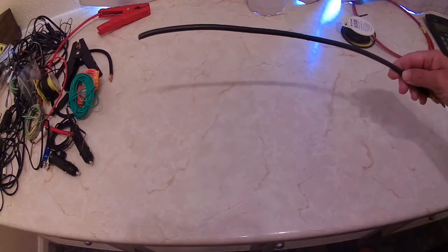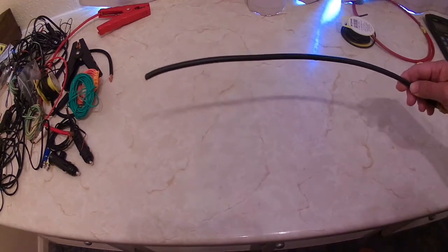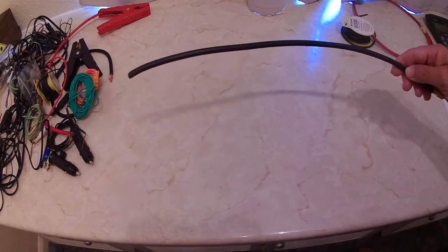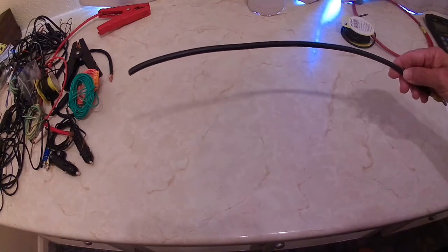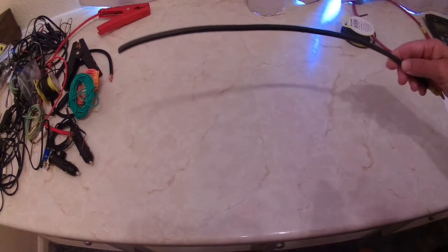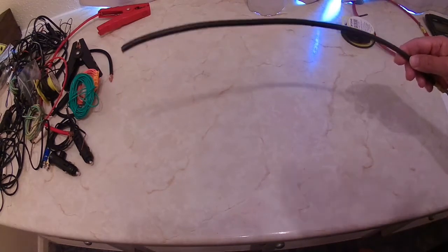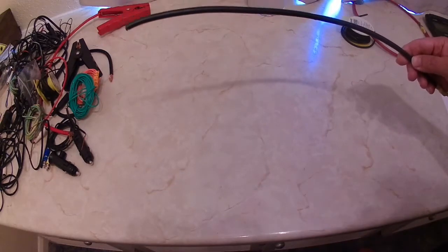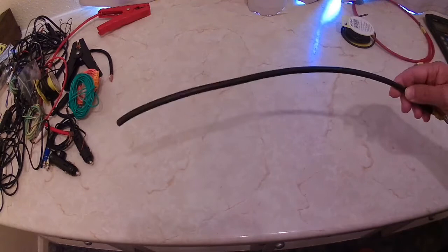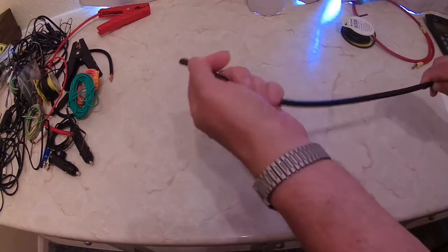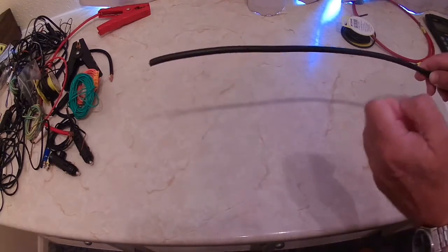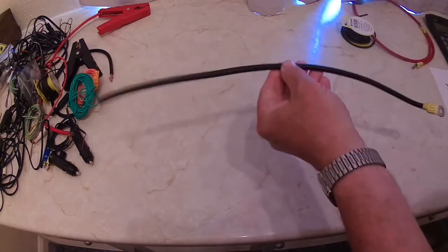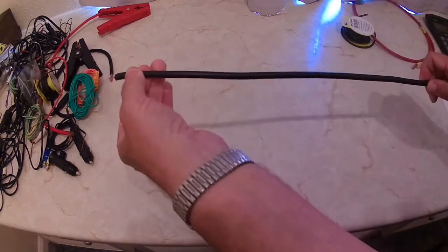This particular cable is quoted at 30 degrees C in free air, and that's where the spec of the cables comes in. So any cables you buy, whatever current rating they are, they're quoted at one temperature and in free air. So they're not against a surface, they're not in plastic or metal conduit, they are simply in free air like this is now.